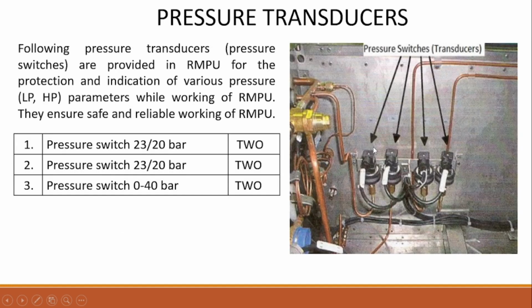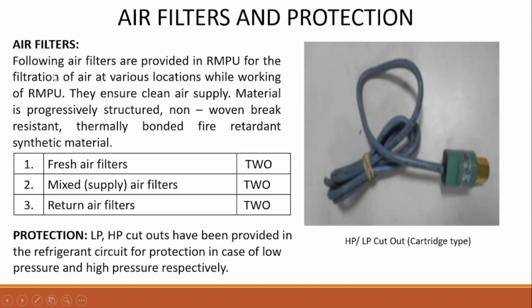As we can see, the following pressure transducers are provided in the RMPU for the protection and indication of various pressure parameters, LP and HP, low pressure and high pressure, while the RMPU is working. They ensure safe and reliable working of the RMPU. Air filters and protection. The following air filters are provided in the RMPU for the filtration of air at various locations. They ensure clean air supply.